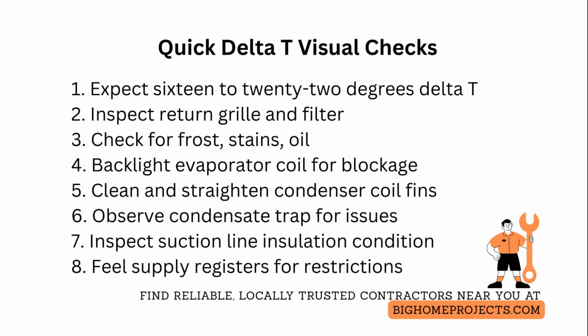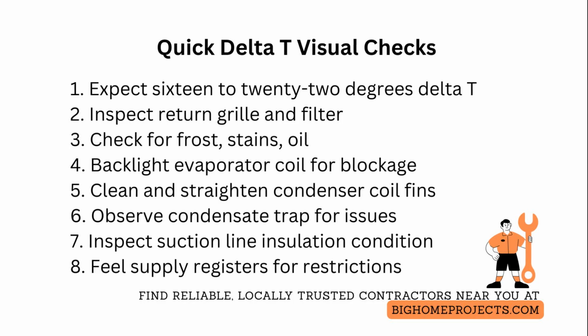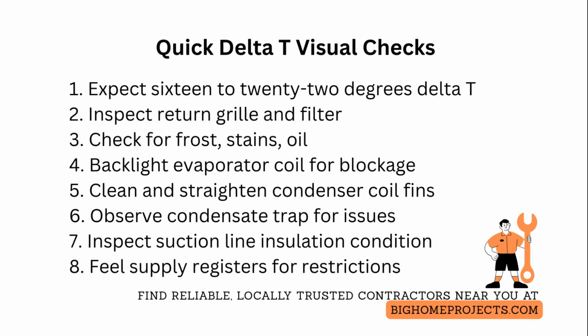Put on a bright headlamp and inspect the return grill and filter first. If a pleated filter looks bowed, gray, or noisy, you likely have static pressure problems choking airflow. Open the air handler or furnace top panel and look for frost, water staining, rust trails, and an oily sheen that can hint at refrigerant leaks.